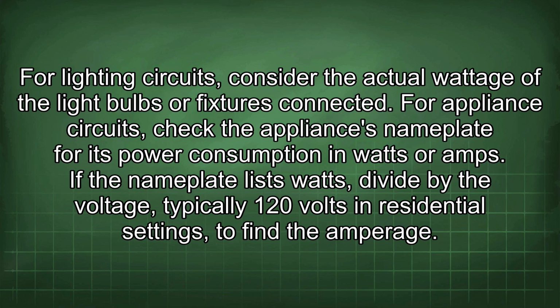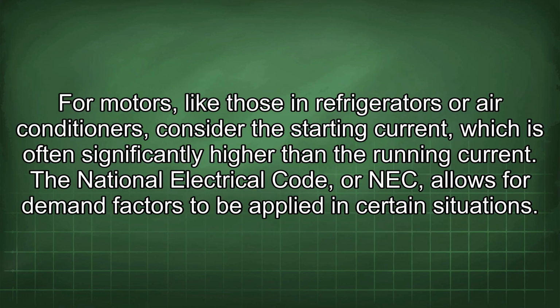If the nameplate lists watts, divide by the voltage, typically 120 volts in residential settings, to find the amperage. For motors, like those in refrigerators or air conditioners, consider the starting current, which is often significantly higher than the running current. The National Electrical Code, or NEC, allows for demand factors to be applied in certain situations.